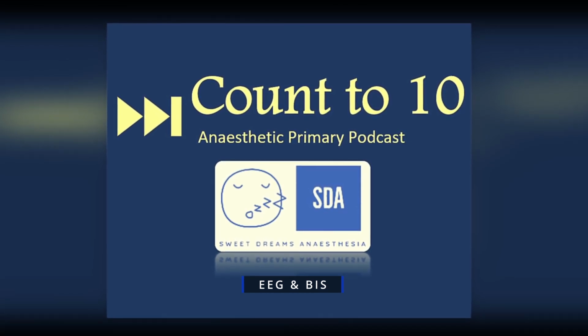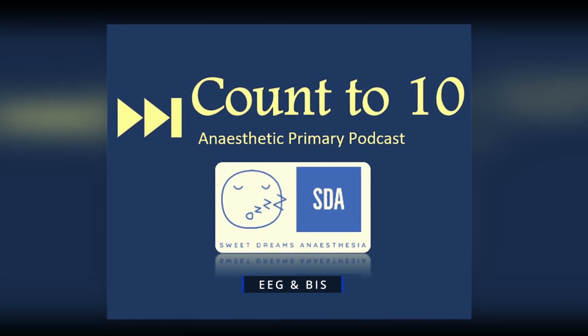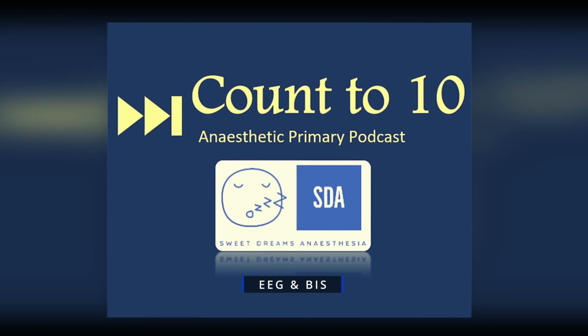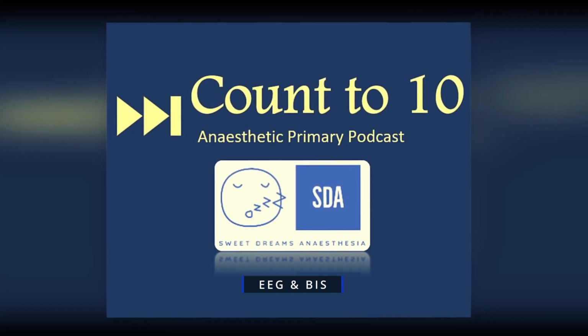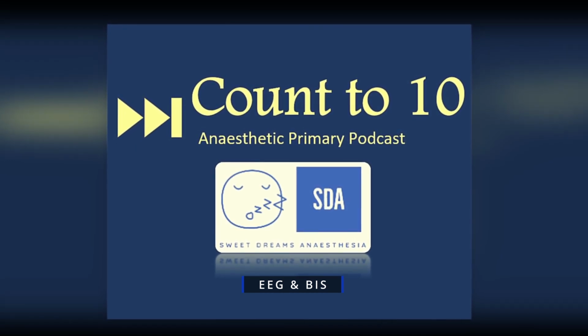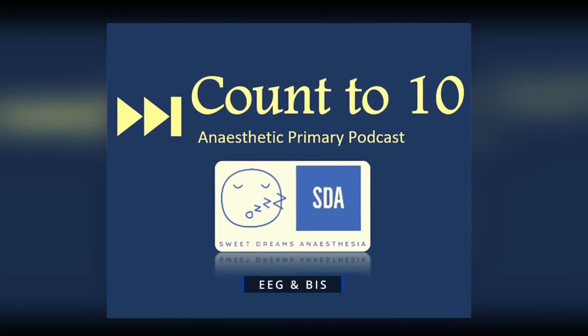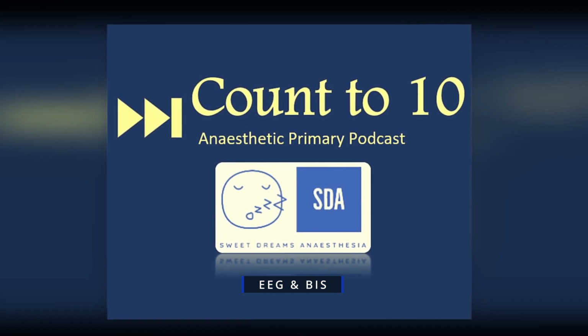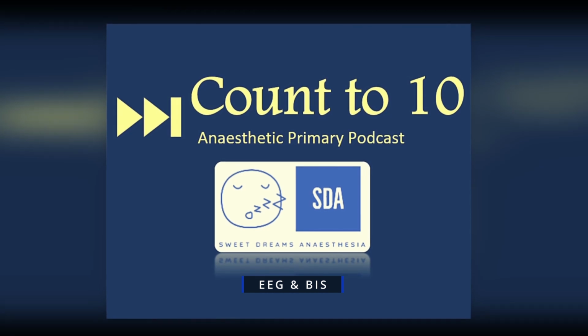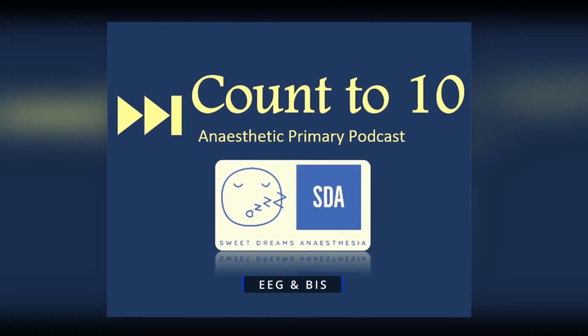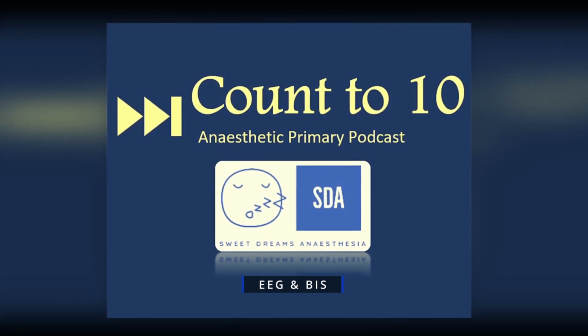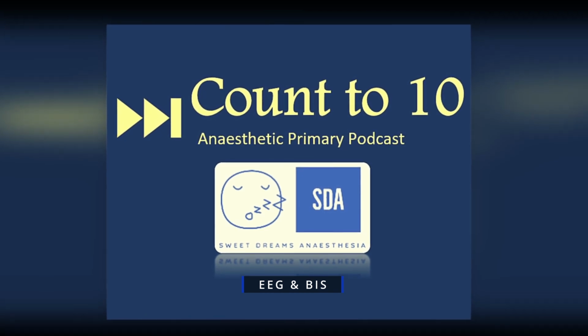And this is a key EEG finding which is characteristic to being under a general anesthetic versus being asleep. So this is one of my pet hates, and I feel so bad to even say that, but it's when people just use the number and don't look at the waveform. While the waveform itself also has lots of errors, if you've got a Bair Hugger on top, if your filters haven't been turned off for the monitor, all these things lead to inaccuracy, but you can look at that waveform to give you additional information and not just look at the number itself.